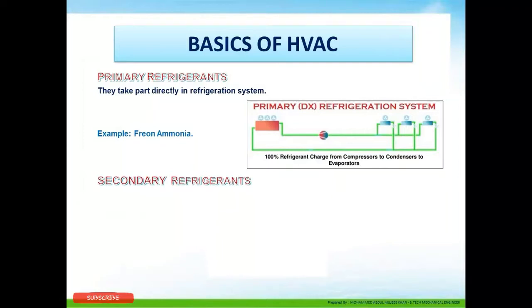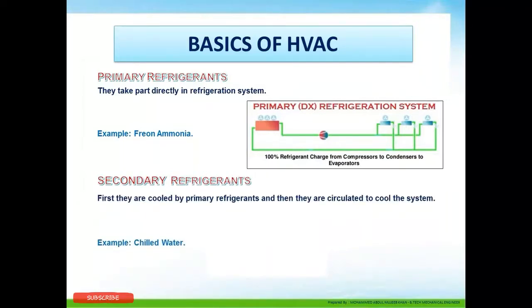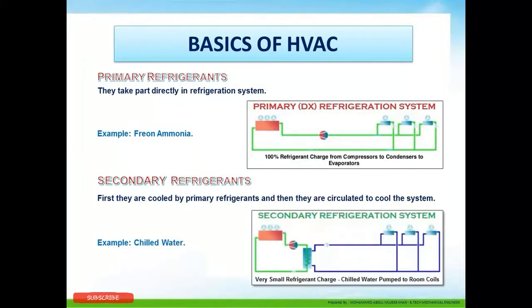The secondary refrigerant is first cooled by the primary refrigerant and then circulated to cool the system - an example is chilled water. As seen in the diagram, the primary refrigerant loop is on the left-hand side and the secondary refrigerant, which is water, is on the right-hand side. When primary refrigerant cooling happens in the evaporator, that cooling is carried forward through the secondary refrigerant (water) to different parts of the HVAC building system.